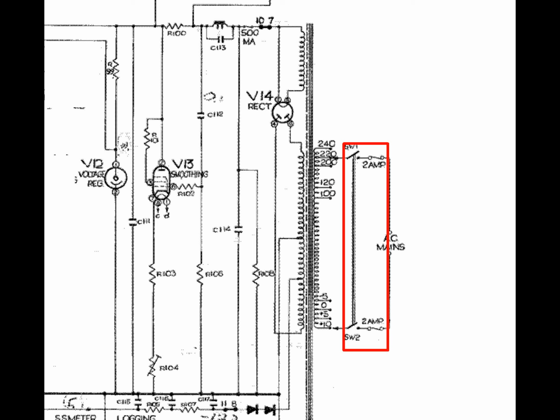In the diagram, we see that there's a mains switch and two fuses on either mains line. The mains also can be connected to the 110 volts point. The wiring inside the transformer for the 110 volts has then to be twice as heavy as the rest of the primary winding. It would also be possible to get around this by having two identical 110 volt primaries and connect them either in parallel for the 110 volts or in series for the 220 volts. In this device, it's possible to fine-tune the set to the local mains voltage by 4 steps of 5 volts each. In the present time, the setting would be 220 volts plus 10 volts in Europe.